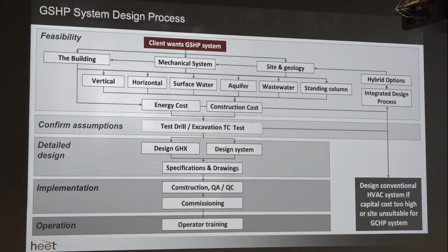But at the end of the day, what matters? Well, what matters is we're trying to save on energy, right? That's why we install these systems. But if it's going to cost you an arm and a leg to do that, it's probably not going to make a whole lot of sense. So to balance the energy cost with the construction cost is the most important thing to make sure that it's practical, right? Because if it's too expensive, nobody's going to buy it at the end of the day. And there are intangibles. A lot of people value carbon in different ways. In Canada, we have a carbon tax, so that's quantified. But the main thing to consider when you're looking at a geothermal system, in my opinion, is to balance these two things: construction cost and then the energy savings that you're getting from that investment, because you're buying an asset, which is that ground heat exchanger.